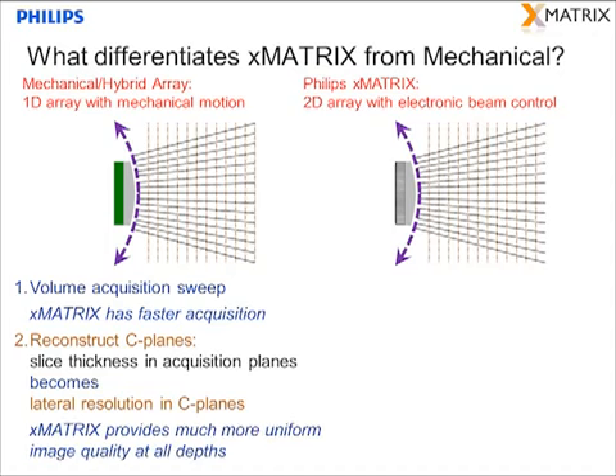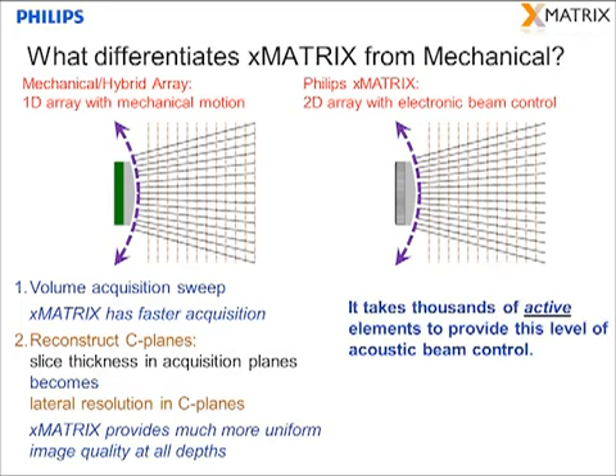The xMATRIX transducer, with its uniform slice thickness, provides good C-plane resolution and much more uniform image quality at all depths. It takes thousands of active elements to provide this level of control of the acoustic beam, and all of the elements are used on every acquisition line. We don't use a subset of the array for different parts of the field of view or a sparse array distributed over the entire surface. Doing so compromises image quality by bringing in noise and clutter. With xMATRIX, the entire array is active all the time.